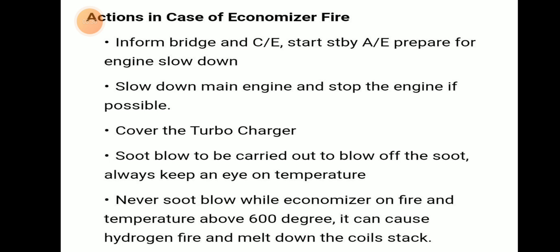Always keep an eye on the temperature. Never do soot blow while the economizer is on fire and the temperature is above 600 degrees Celsius.